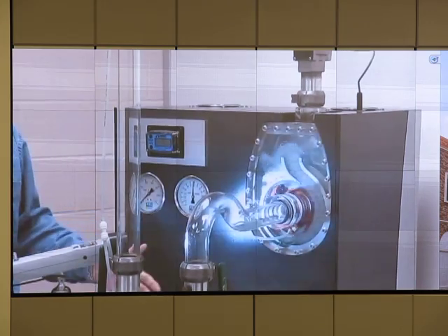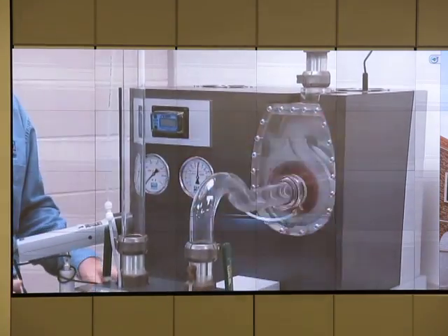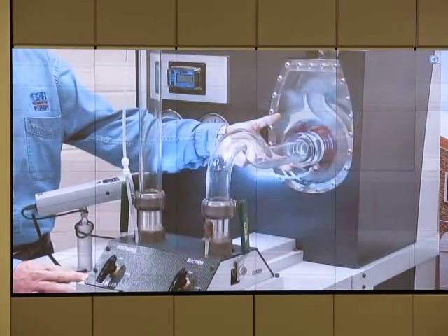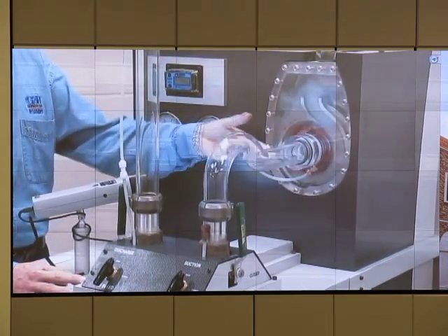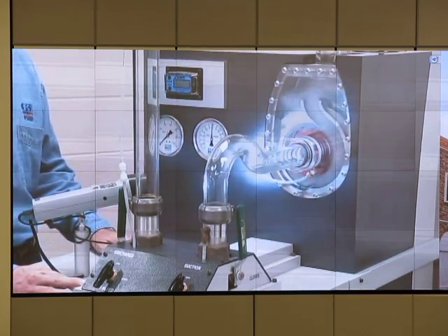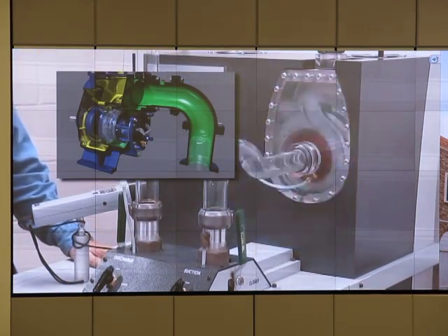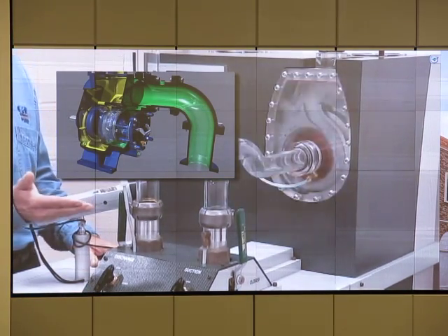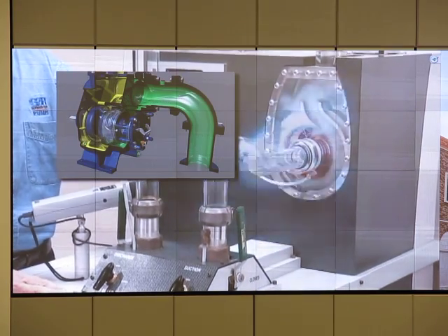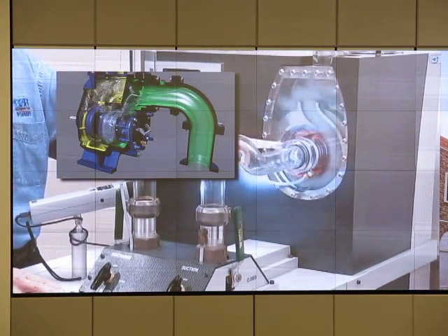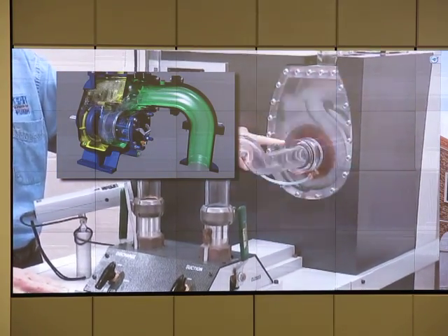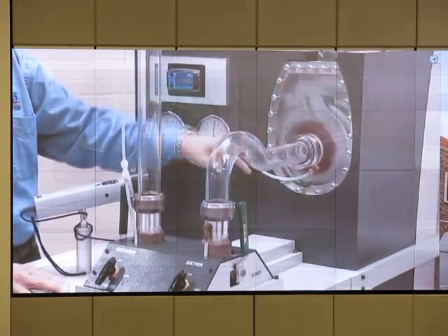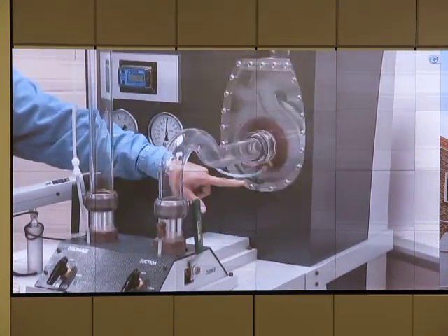Due to differential in pressure, atmospheric pressure that we live around every day is higher than the lower pressure created at the eye of this impeller. Due to that differential in pressure, atmospheric pressure outside begins to force liquid up the suction pipe. As liquid moves up the suction pipe, it pushes all the air ahead of it into the volute casing where it is handled through the recirculation process. Again, the air is handled off the top and the heavy water recirculates back down into the volute scroll area.